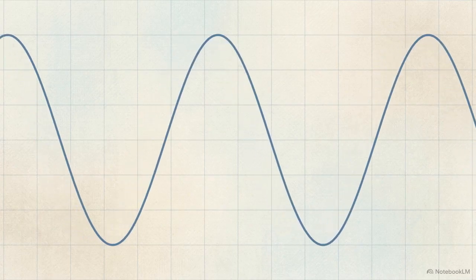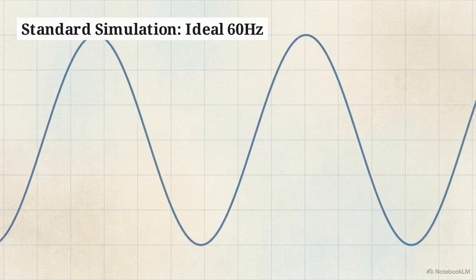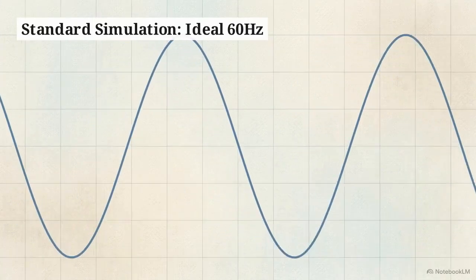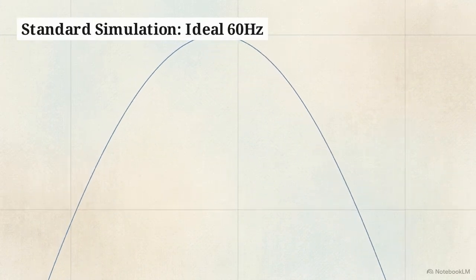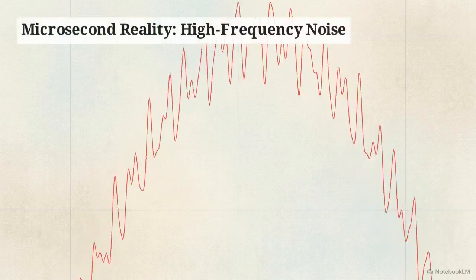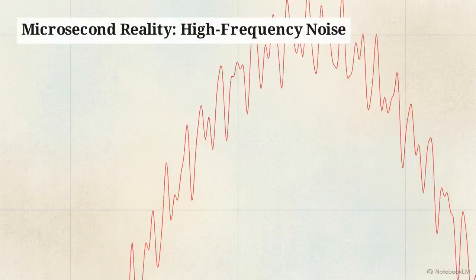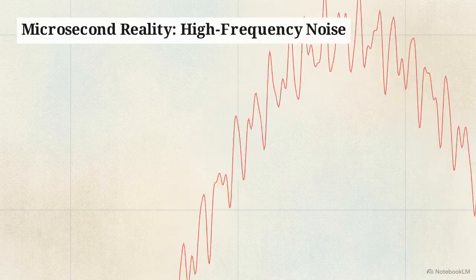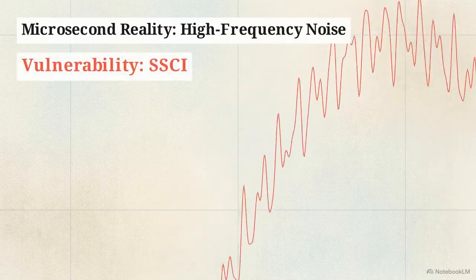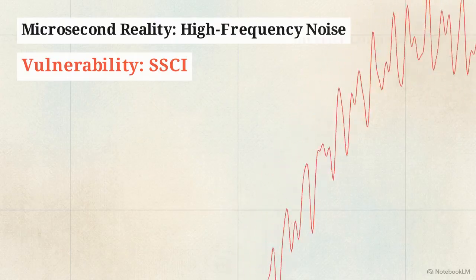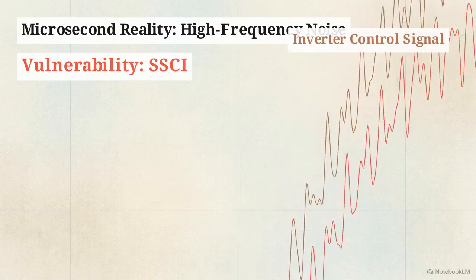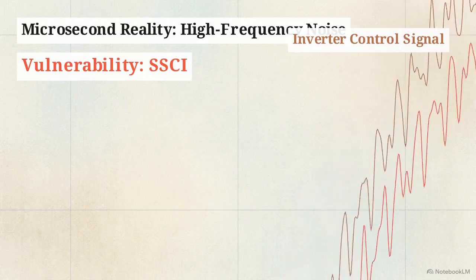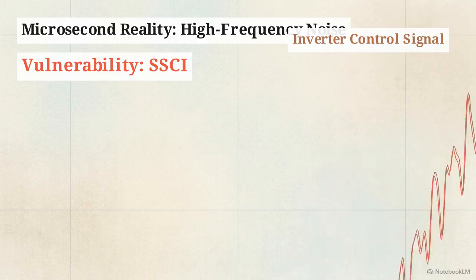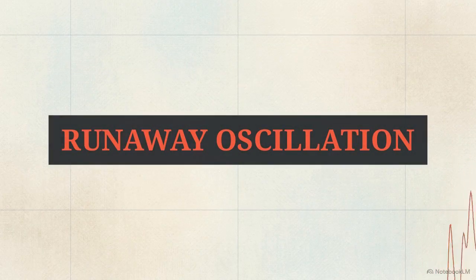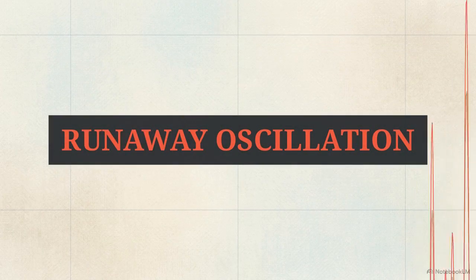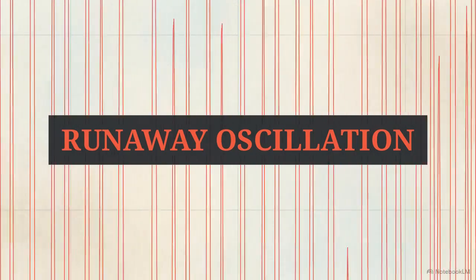In a standard simulation, grid voltage looks like a perfectly smooth, continuous 60 Hz sine wave. But if you zoom in to the microsecond level, you find that the actual waveform is chaotic, filled with jagged, erratic, high-frequency spikes. These microspikes introduce a unique vulnerability called subsynchronous control interaction, or SSCI. SSCI happens when an inverter's high-speed software control loops accidentally sync up with the grid's natural resonance at lower frequencies.